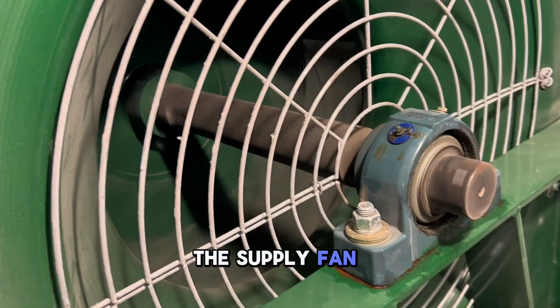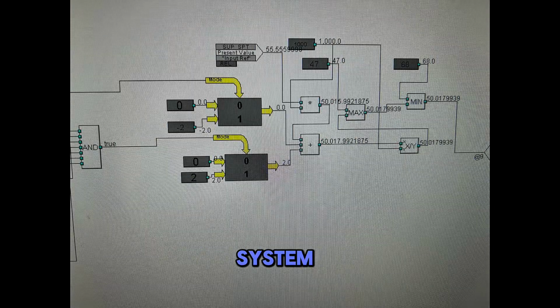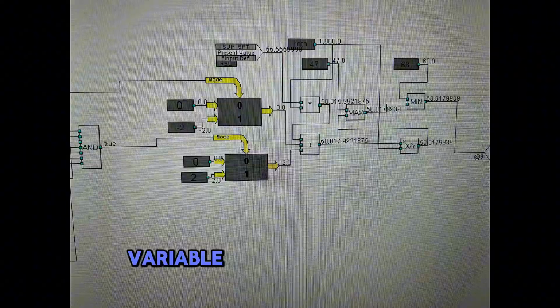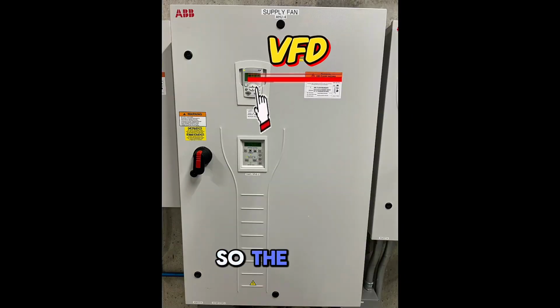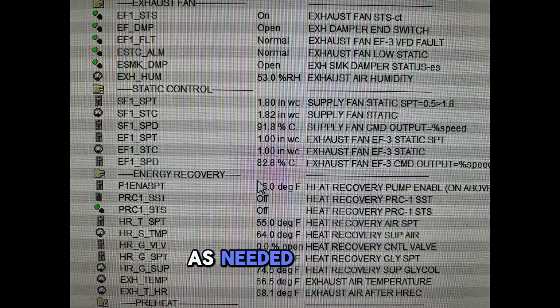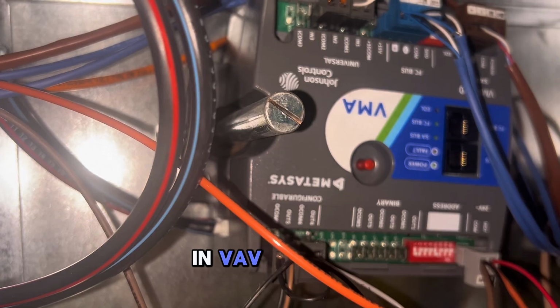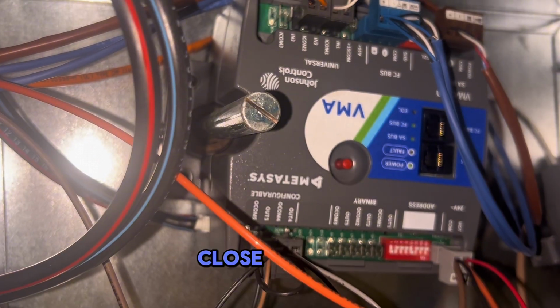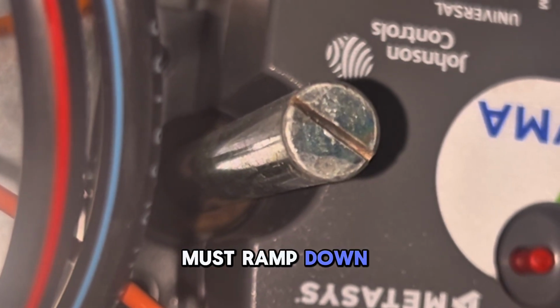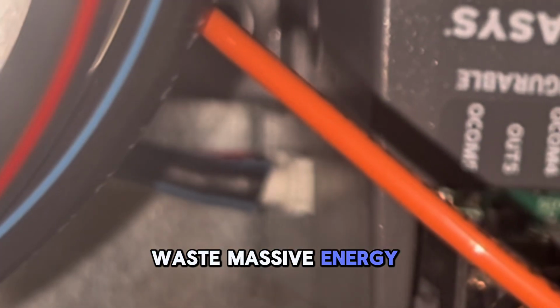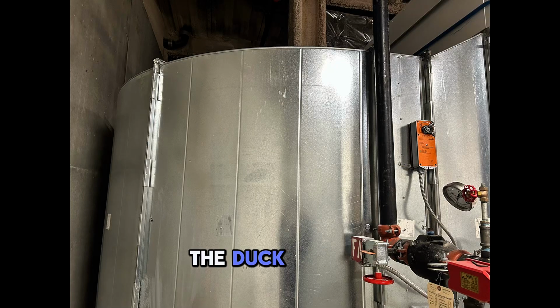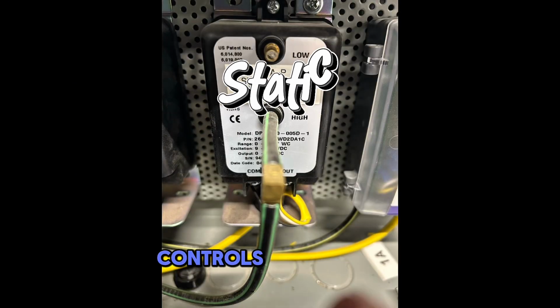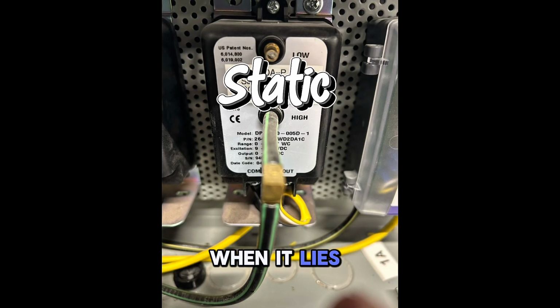The supply fan is the muscle of the whole system. Modern units use variable frequency drives, so the fan speed can go up and slow down as needed based on a static set point. This is critical in VAV systems. When VAV boxes close, the fan must ramp down or you will waste massive energy. I'll show you the duct static pressure sensor that controls everything and what happens when it lies.